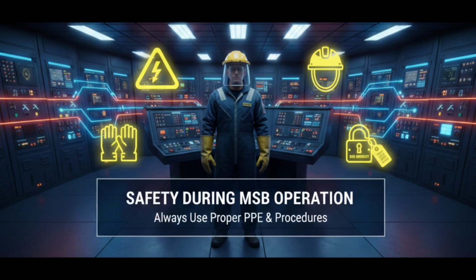Safety during MSB operation. Safety is the top priority when operating the main switchboard. Always wear proper personal protective equipment, including gloves and safety shoes. Never close a breaker without checking synchronization. Avoid touching live parts. Follow lockout and tagout procedures during maintenance.